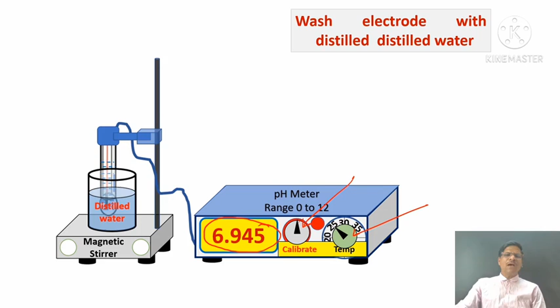I will place the Coca-Cola on the magnetic stirrer and I will dip the pH sensor, or the combined glass electrode, into it. Okay, so the reading is changing. We have to wait till the reading becomes constant. Okay, so the reading is constant and it becomes 2.831. What does it mean? It means that the pH of the Coca-Cola cold drink is acidic, and it is 2.831. Okay, so you have to search and give the reason why Coca-Cola is acidic in nature. I will not explain here. It is your task.